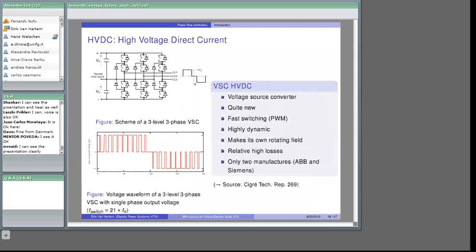Just want to mention that HVDC is a special power flow controller. It allows full and independent active power flow control. So if you have a phase shifting transformer or a TCSC device, then the flow to the line where this device is placed in is dependent on the rest of the system. You can control it, of course, but it's still dependent on the entire system power flows, while the DC system cuts the system in two parts and makes the power flow control fully controllable.